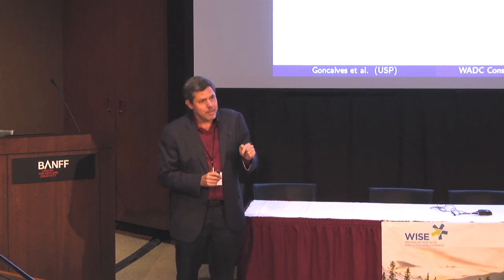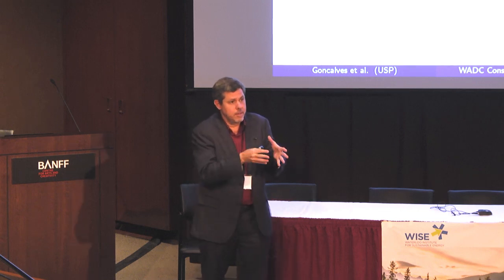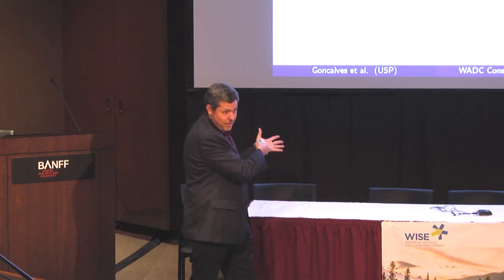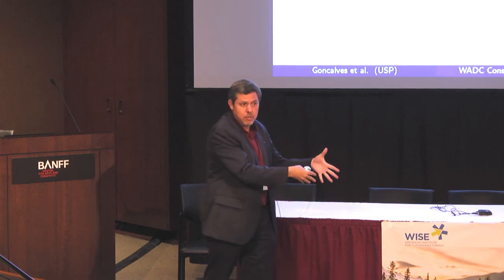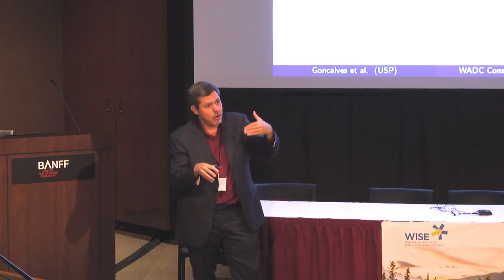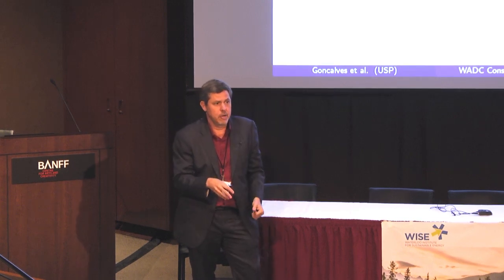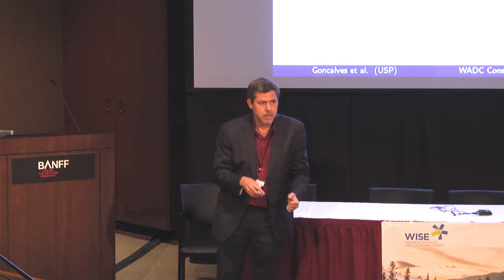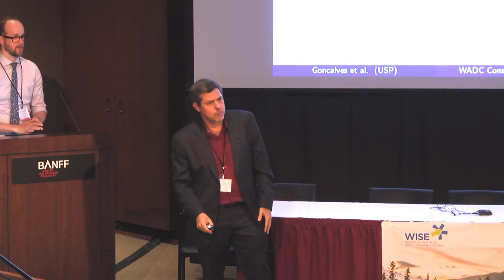They change the equilibrium point in a way that you cannot predict with deterministic methods. So that's why we actually have to sample to find out the problematic scenarios and include them in the design, to make sure that the effect of the wind power over the electromechanical oscillations is accounted for. And at the end, you have a robust design. The whole purpose of this is robustness.